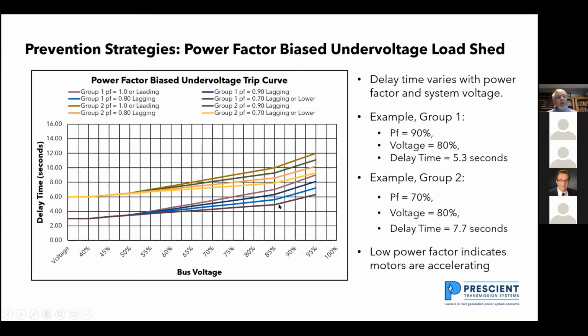This is a group 1 setting. So group 1 has 4 characteristics. It has 100% power factor, 90, 80, and 70% power factor. And if I'm at 90% voltage, and I should say 80% voltage, and 90% power factor, that would be right here. I can allow this to run for a longer time than if I've got a poorer power factor.